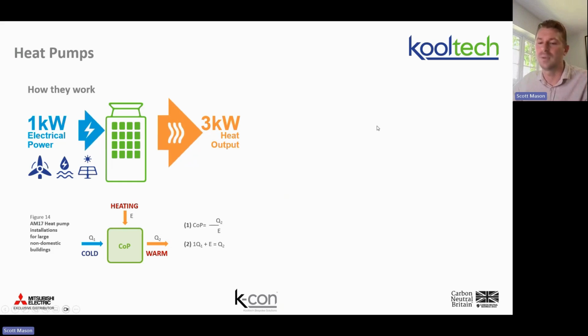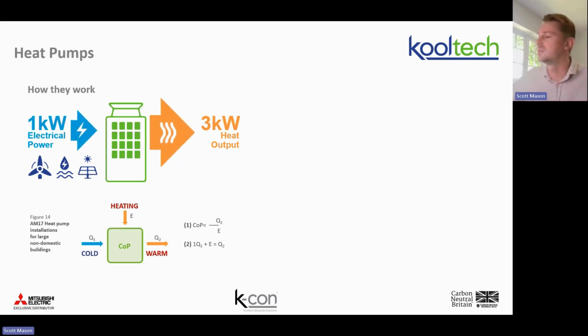If you're looking at decarbonising a building, what you're really going to be looking at is the seasonal coefficient of performance. That's your SCOP. And that takes into account different flow temperatures for that heating circuit, or a fixed figure of 55, 45, or 35, depending if it's a high, intermediate, or low temperature SCOP. And it'll also take into account different outside air temperatures through the course of the year. Now, that's important because that means that the efficiency value is going to be real.